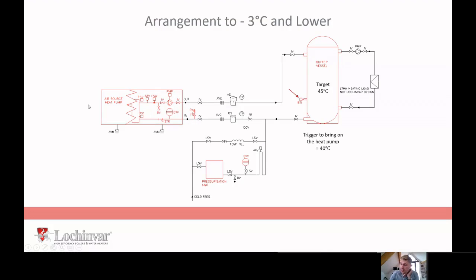So if I've got a 45 kilowatt heat pump, I'm going to have a 400 litre thermal store. I'm going to say there's 50 litres of water in our pipe, so no worries. And the heat pump is going to monitor a sensor and maintain a temperature in that tank. The heat pump's going to flow. If we've got a target temperature of 45 degrees, it's a low temperature circuit we're serving, probably radiators. But to achieve that, what the heat pump will do is it will flow at 47 degrees and it will return at 42. The heat pump is going to work on a 5-degree delta T.